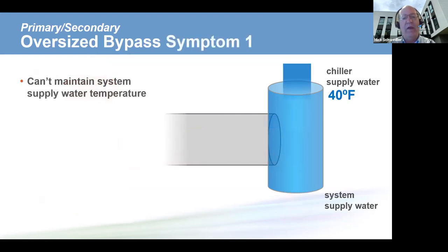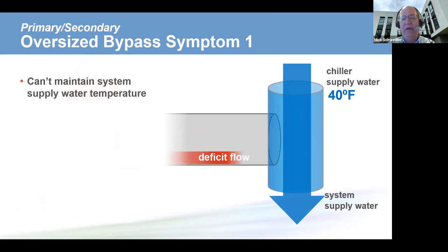Well, we have 40 degree chilled water being made. It mixes with return water from the system, and we are not able to maintain the supply water temperature going out to the system. So that's one of the symptoms. Even though our chillers are making their chilled water set point, we can't get that set point going out to the system. It's not the pump heat. A lot of times the issue is an oversized bypass line.